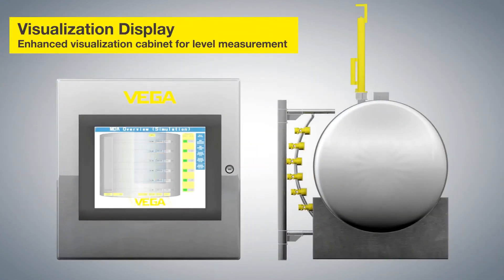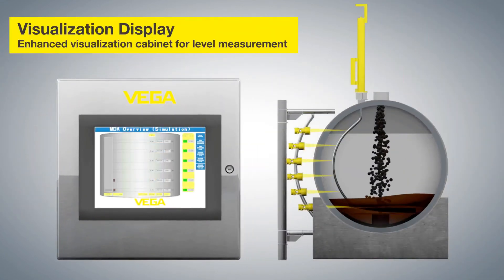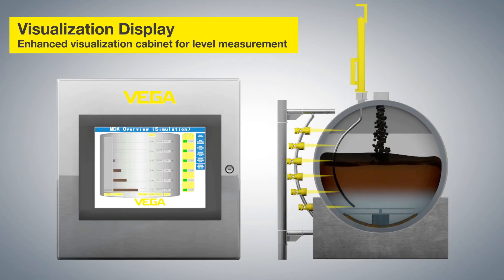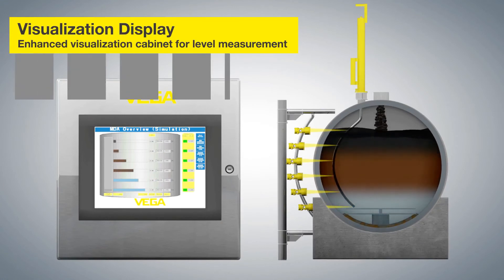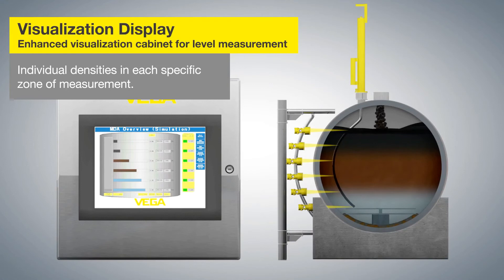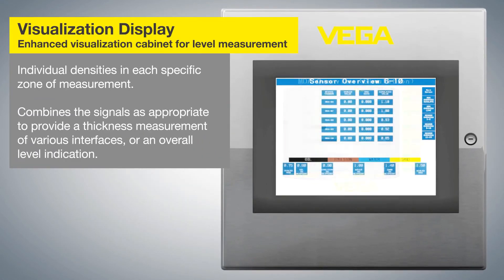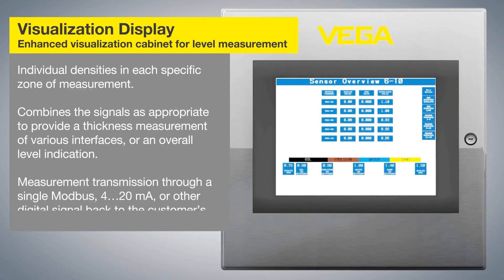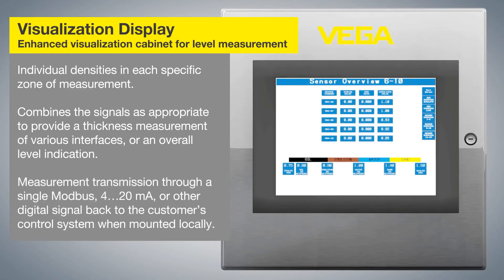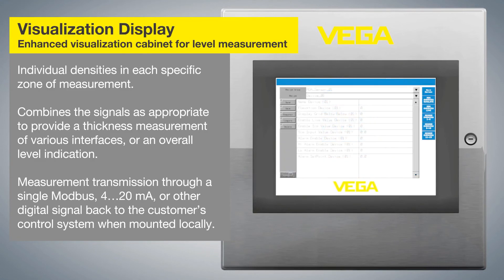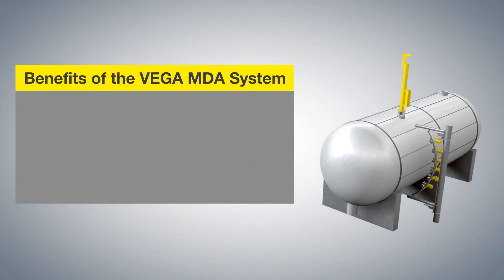Visualization Display: An enhanced visualization cabinet for level measurement displays individual densities in each specific zone of measurement. It combines the signals as appropriate to provide a thickness measurement of various interfaces, or an overall level indication. Measurement transmission occurs through a single Modbus, 4 to 20 mA, or other digital signal back to the customer's control system when mounted locally.